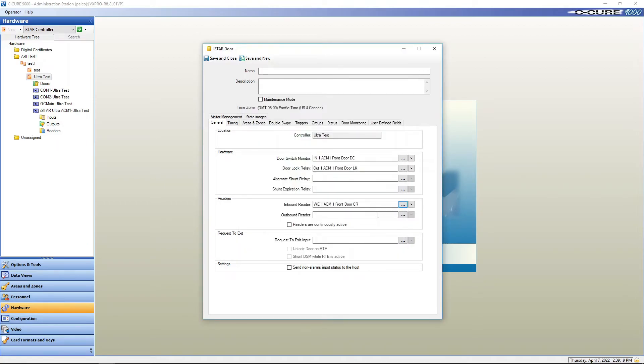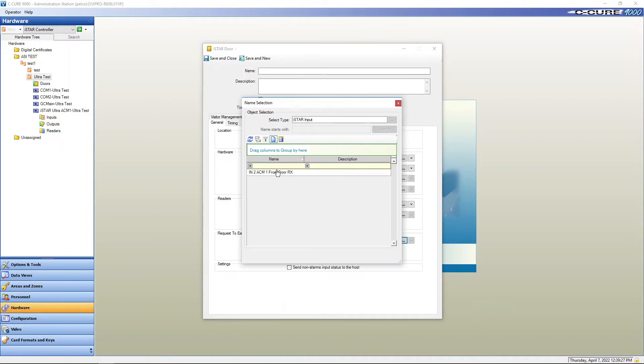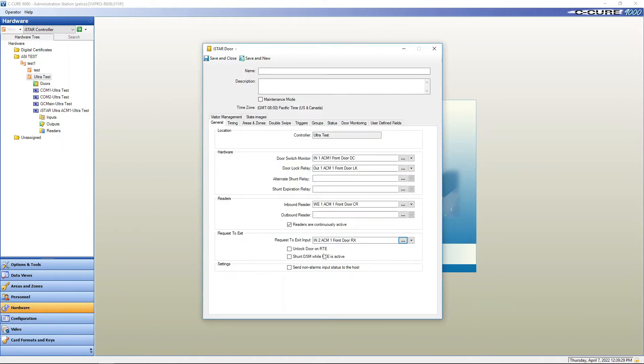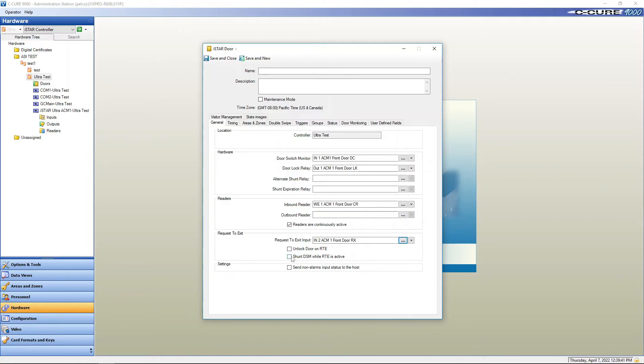We could do an outbound reader if we had a reader on either side of the door. We wouldn't be using a request to exit then. We're going to say readers are continuously active. And then our request to exit we're going to put in there. And we can have that request to exit unlock the door every time it's activated. We're going to set it up to shunt and we're going to save and close.